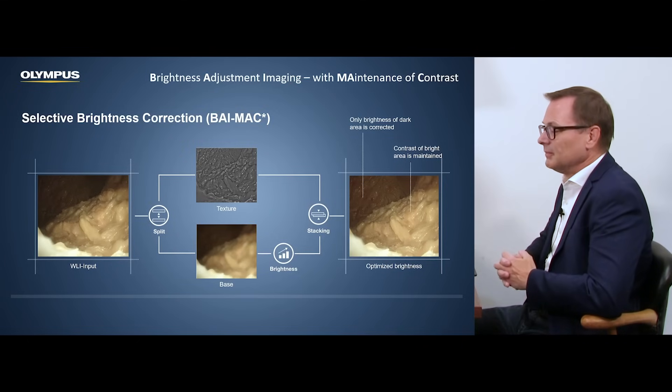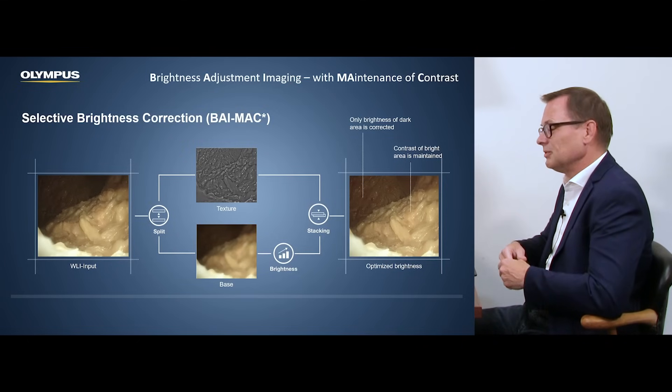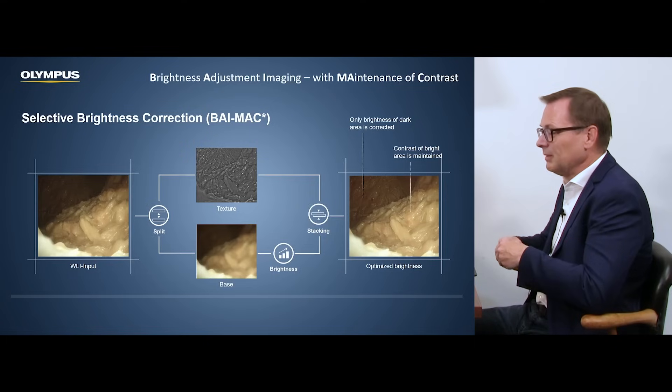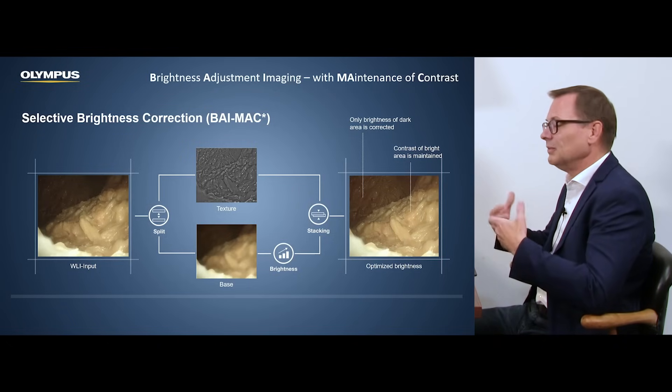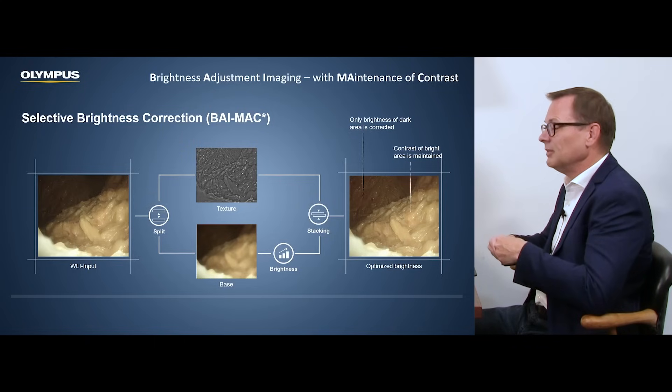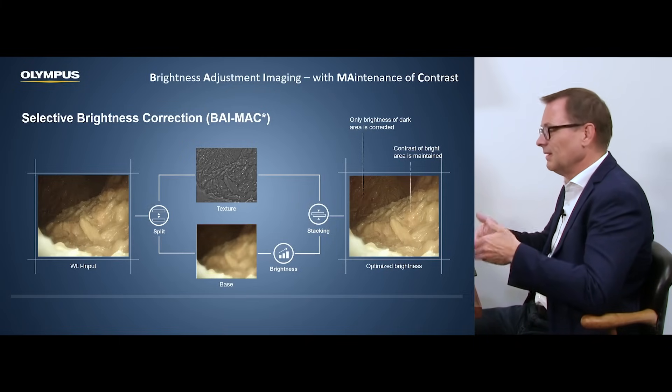And how does it work? On the left side there is an image which is nicely illuminated in the front part and quite dark in the back, which is very typical. If you would simply increase the brightness of the light source, then yes, you have better illumination of the back part, but you have a white-out in front and then you don't have good visibility there. So the BAI-MAC function technologically splits the image into a texture part and a brightness part, and then you can adjust the brightness separately from the texture. This is important because on the white light image as it is, any change in brightness or texture would influence the other.